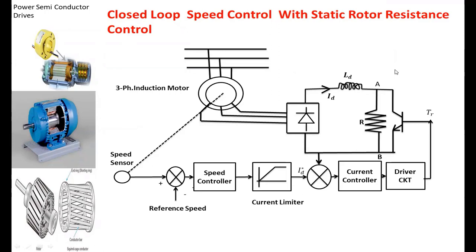Now we are going to see the closed loop control of the static rotor resistance. Here the same circuit is taken. This is the three-phase supply given to the stator of the induction motor. This is the rotor. The rotor power is converted into DC power by means of a diode rectifier circuit, and that is given to the external resistance. Across the external resistance we connect a BJT. The gate pulse for the BJT is used to control how much resistance is added into the rotor circuit. This choke reactance is placed to maintain a smooth DC link current.